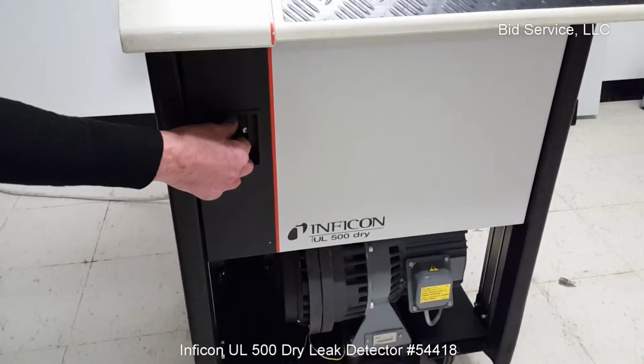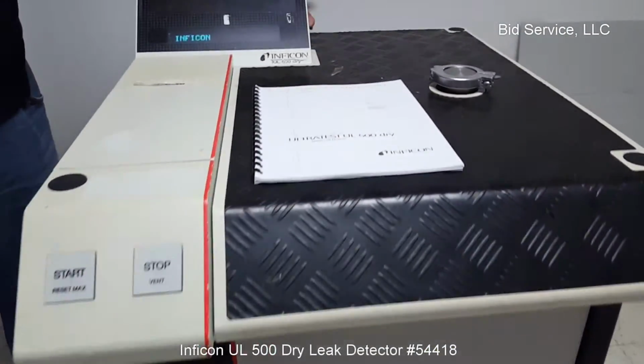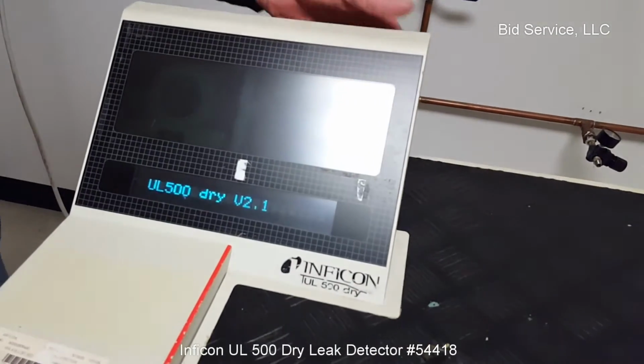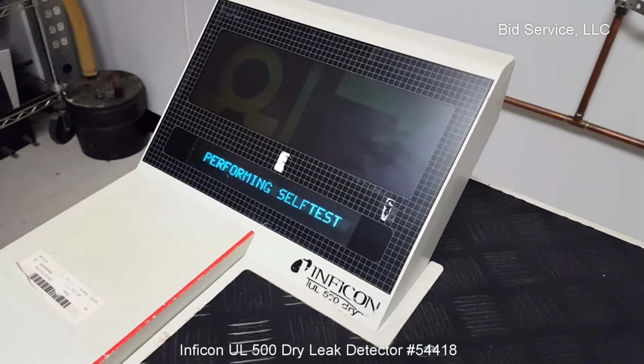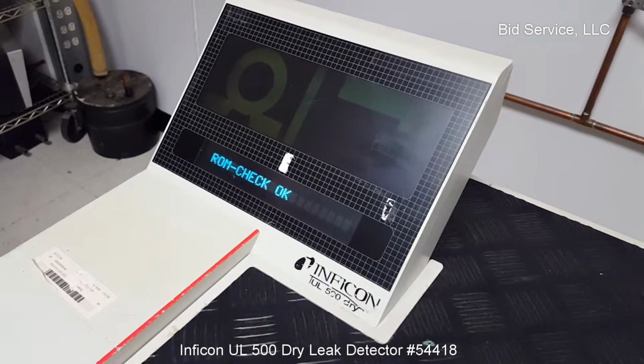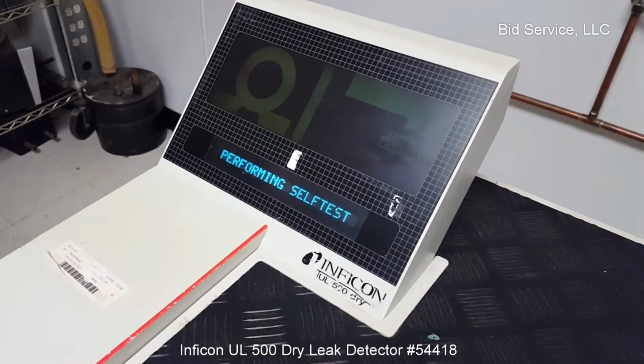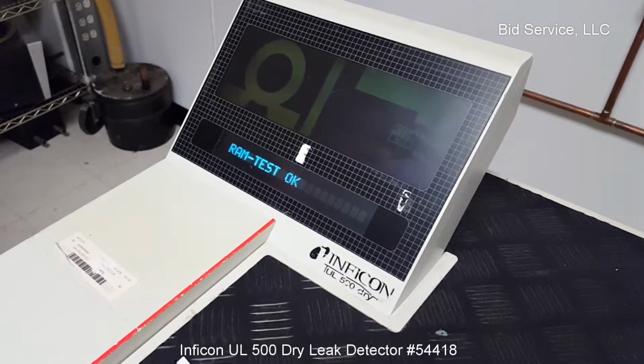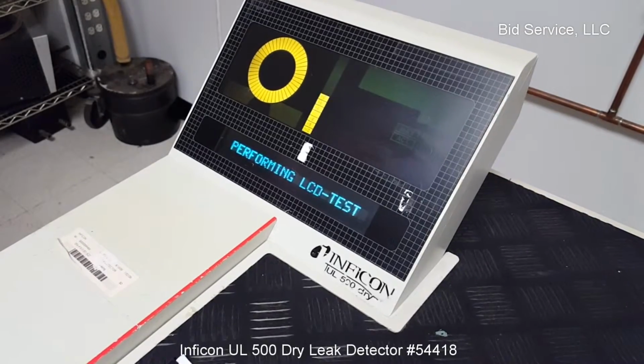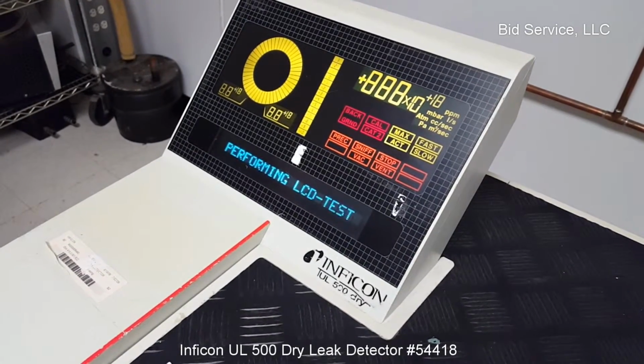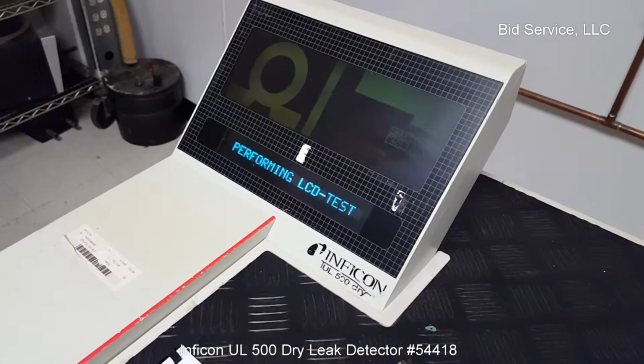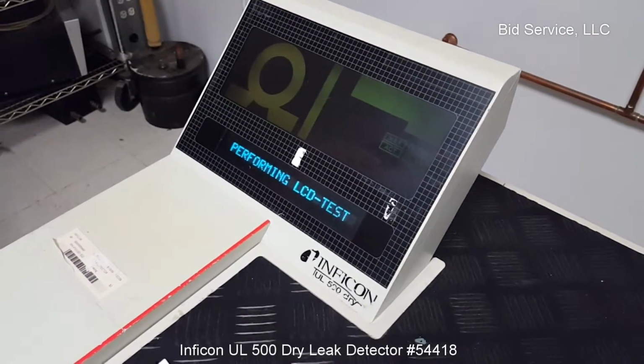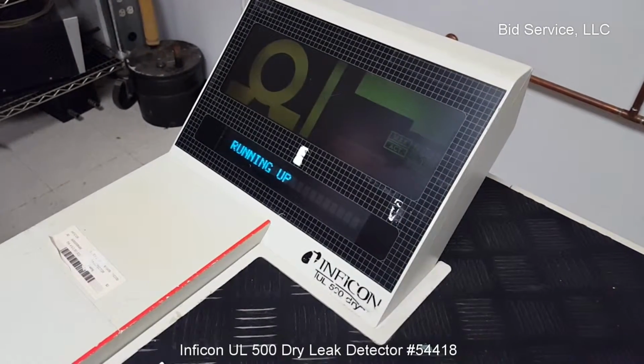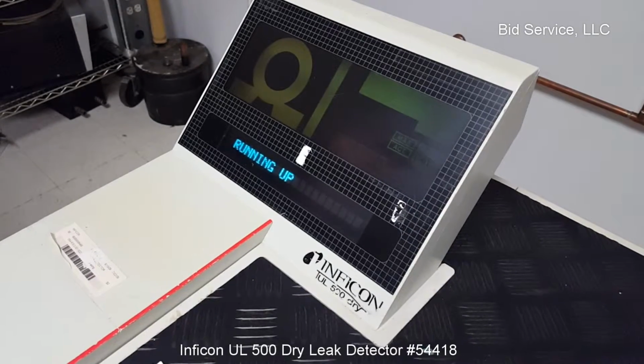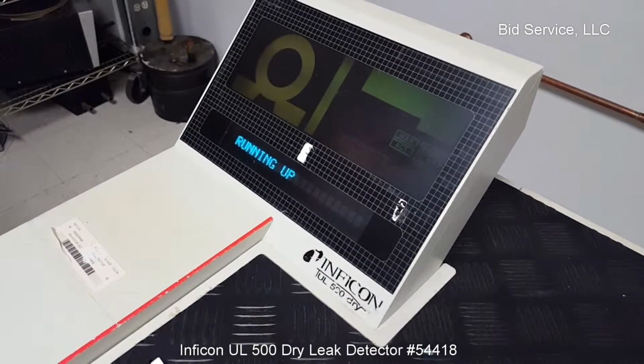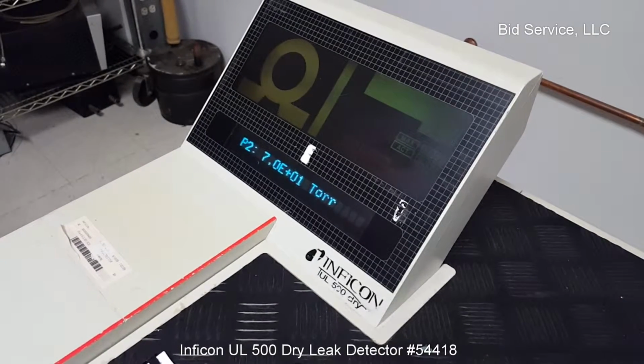Again, here's the main power switch. Once we turn it on, the system will boot up and also perform its own self-tests. There are no errors. Now the system will automatically start the pumps and start to pump down the mass spec.